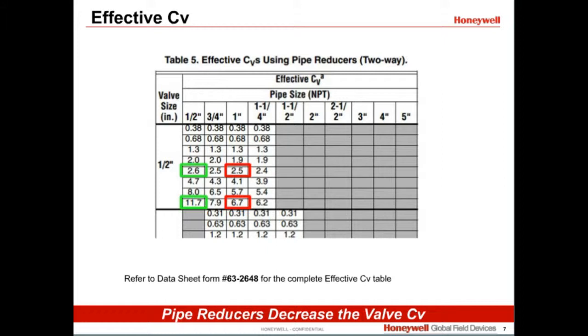It is important to check effective CV whenever pipe reducers are used with ball valves. Be sure that an undersized valve has sufficient capacity at maximum load to heat or cool the space.